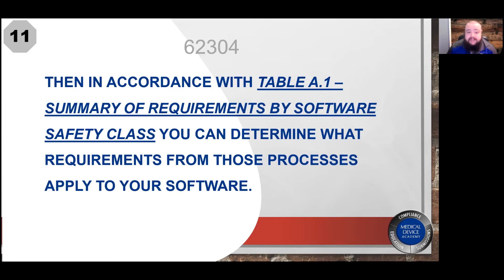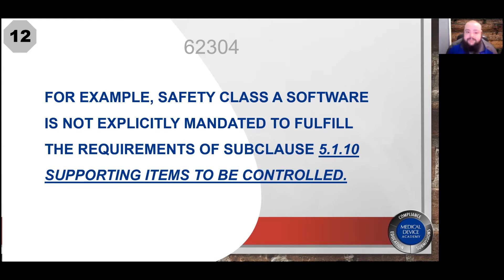Once you've assigned a software safety classification to your software system, you'll move to Table A1, which is the summary of requirements by software safety class. That table explains which requirements from those processes apply to your software based on the software safety classification. For example, if your software system has a software safety classification of Class A, it is not required to fulfill the requirements of sub-clause 5.1.10, supporting items to be controlled. The individual requirements of all five processes are dependent upon the classification of your software.